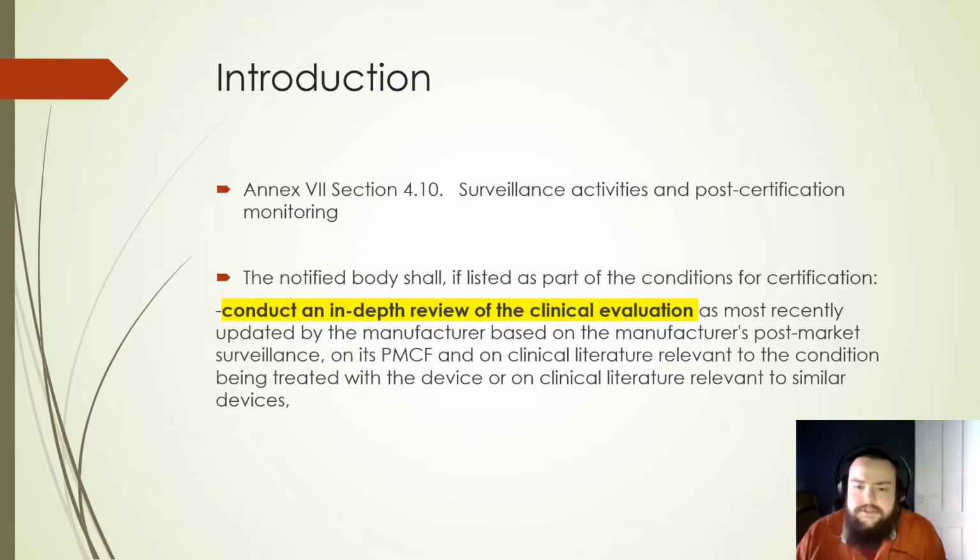So one of the reasons to qualify any outside help you bring in to work on your project for your search and review and to update your clinical evaluation report is that your notified body is going to take a look at this information. So you need to approach it in a manner that any data that's gathered needs to be able to maintain its scientific and clinical integrity. This is not work that's going to be put into a filing cabinet and collect dust, never to see the light of day again. Your notified body is going to evaluate the work that was done.